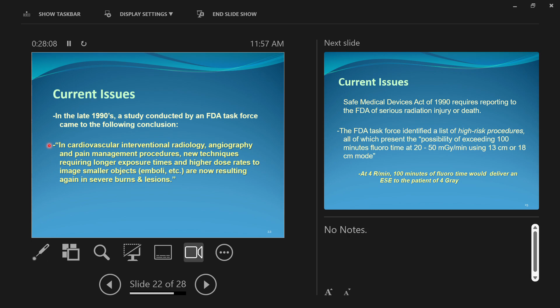And the FDA task force identified a list of high-risk procedures, all of which present the possibility of exceeding 100 minutes of fluoro time. Remember, 5-minute alarms, right? That alarm's going to come on 20 times during a 100-minute procedure. 100 minutes of fluoro time or more at 20 to 50 milligray per minute, which comes out to quite a lot. You can add that up pretty quickly. 20 to 50 milligray per minute for 100 minutes. It's going to add up very, very fast, right?